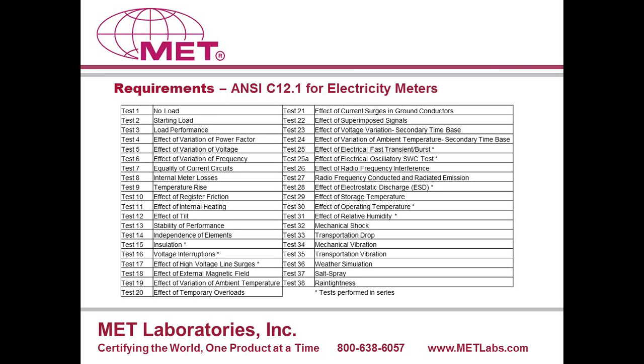But in terms of the tests that are required, they're very, very similar, if not identical, to the 38 tests that are shown here. So depending on the product that we would be testing, whether it be sub-metering or revenue generation metering, several, if not all of these tests may be required. So essentially what has to happen is you take a look at the product, its features and functionality, and intended installation, and you determine from there which of these tests are applicable.